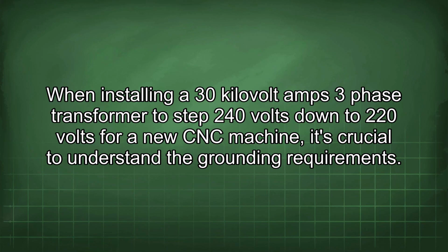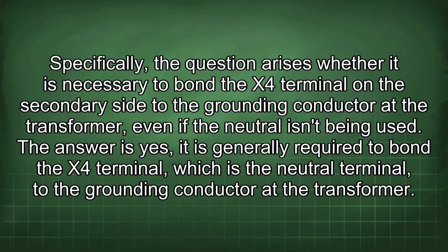When installing a 30 kVA 3-phase transformer to step 240 volts down to 220 volts for a new CNC machine, it's crucial to understand the grounding requirements. Specifically, the question arises whether it is necessary to bond the X4 terminal on the secondary side to the grounding conductor at the transformer, even if the neutral isn't being used. The answer is yes, it is generally required to bond the X4 terminal, which is the neutral terminal, to the grounding conductor at the transformer.